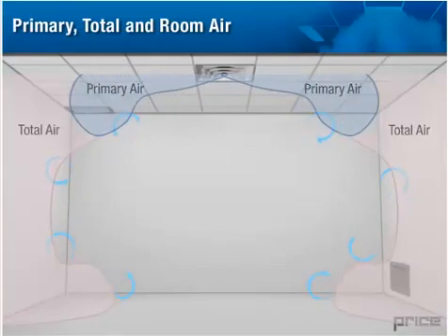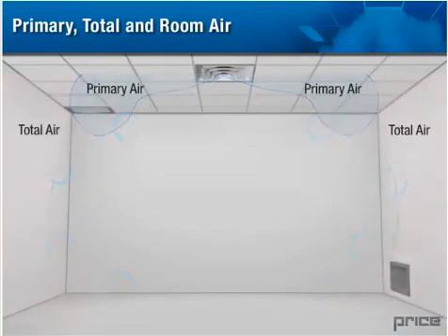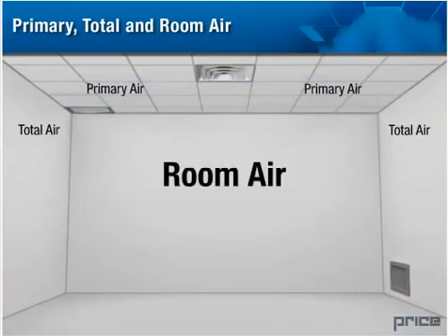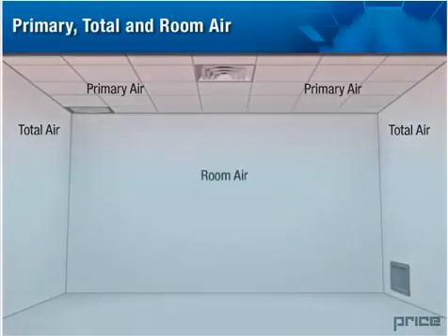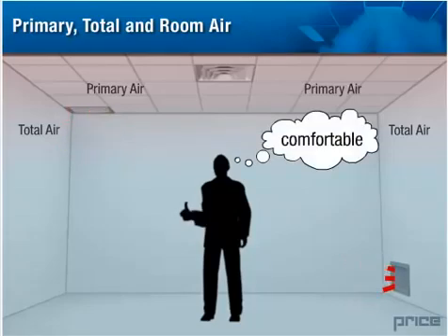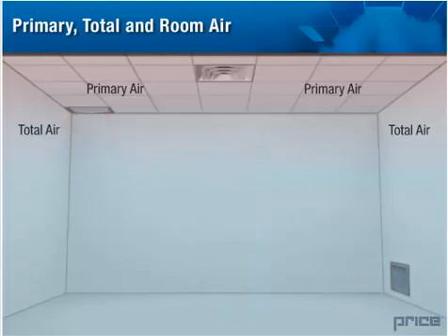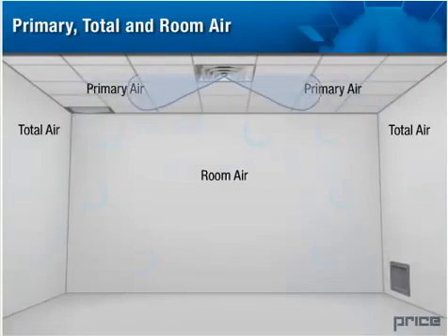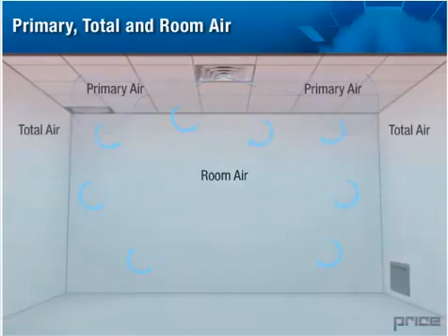The room air is the medium through which all metabolic heat transfers occur, and thus the most critical factor in controlling human comfort. The room air consists of all the other air within the space not included in the total air package. Proper air distribution conditions the room air and maintains draft velocities and temperatures within comfort levels. Room air movement is created by its gradual induction into the primary air stream, forming the total air stream. It is this constant mixing that provides the mechanism for heat transfer between the primary and room air.